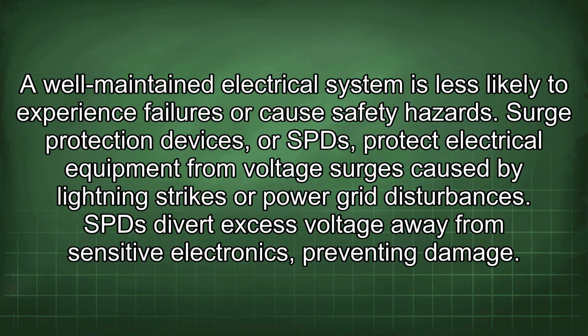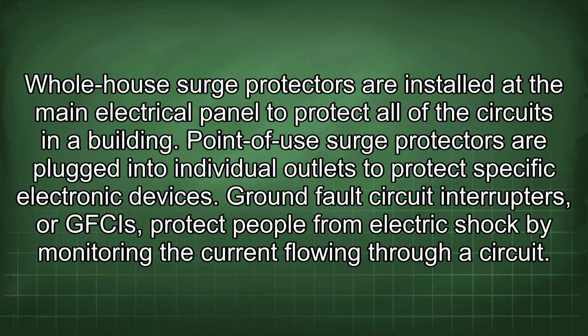Surge protection devices, or SPDs, protect electrical equipment from voltage surges caused by lightning strikes or power grid disturbances. SPDs divert excess voltage away from sensitive electronics, preventing damage. Whole house surge protectors are installed at the main electrical panel to protect all of the circuits in a building. Point-of-use surge protectors are plugged into individual outlets to protect specific electronic devices.